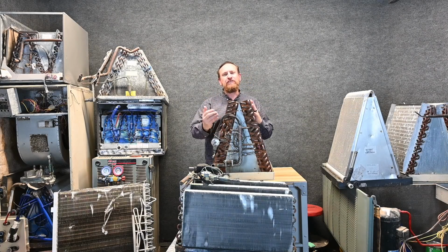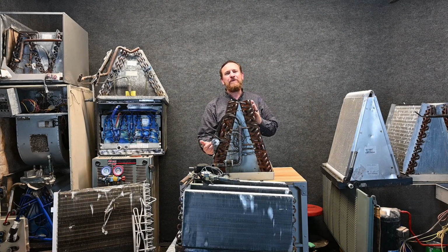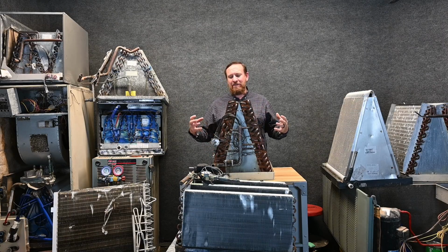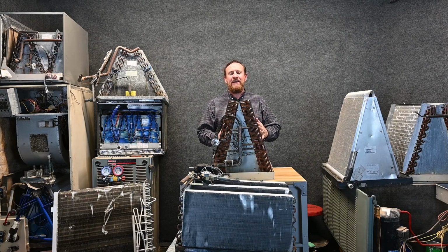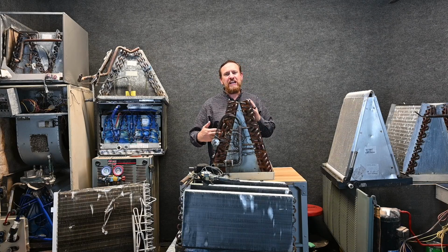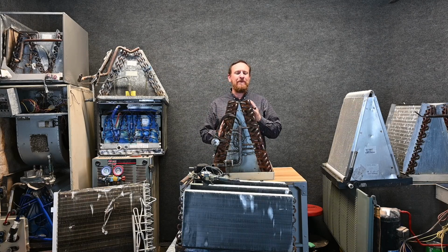So the refrigerant that's flowing through here is coming in as a liquid saturation mixture. And that refrigerant is going to be not just evaporating, not just slowly changing state, but violently boiling inside. The word boiler was already used, so we call it an evaporator. That refrigerant's changing state from a liquid to a vapor. And every time a substance changes state from a liquid to a vapor, it absorbs heat.